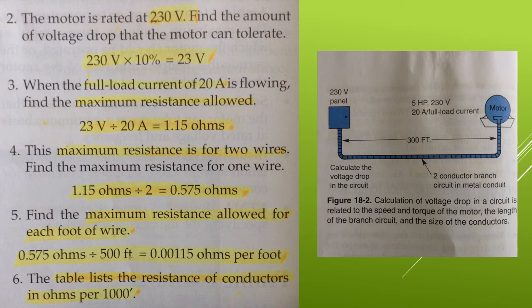Step 3, when the full load current of 20 amps is flowing, find the maximum resistance allowed. So for that, we divide 23 volts divided by 20 amps. 23 divided by 20 equals 1.15, and that is in ohms.